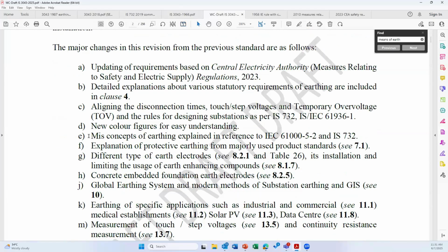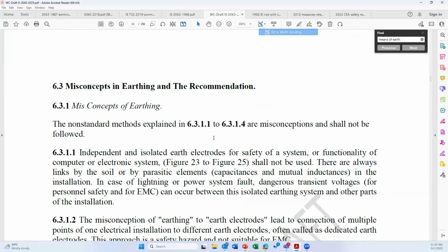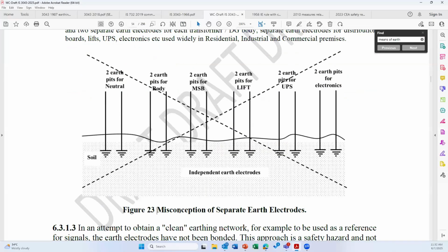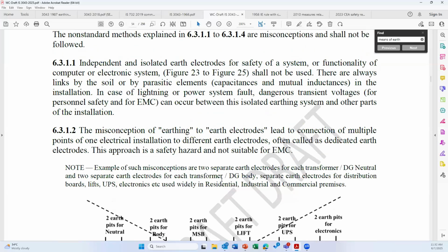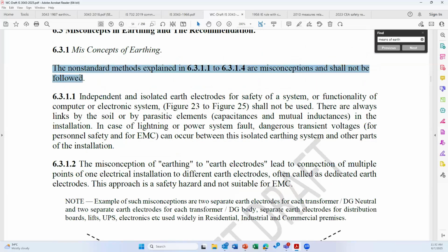Similarly, the next improvement is the misconception of earthing, explained in reference to IEC 61000-5-2 and IS 732. As I explained to you, everywhere we have the wrong idea of doing wrong earthing. Now this picture has been included. This is figure 23, misconception of separate earth electrode. So if the electrical inspector or any safety officer, safety auditor, or maybe factory inspector comes to you and asks for too many earth pits, you have to show this particular picture and tell them, sir, this is wrong. This is the reason for all the accidents. You can also read the contents here, misconception of earthing. The non-standard methods explained in 6.3.1.1 to 6.3.1.4 are misconceptions and shall not be followed. Shall not be followed means strictly you should not do.